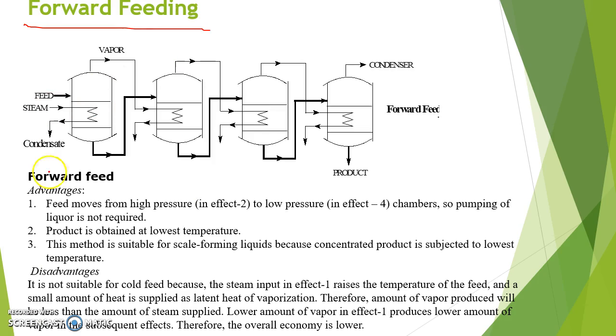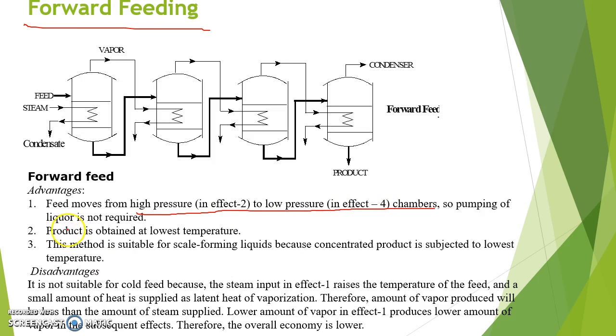In forward feeding, the feed enters the first effect evaporator and the product is collected from the last effect evaporator. The advantages of forward feeding are: feed moves from high pressure to low pressure chambers so pumping of liquor is not required, and the product is obtained at the lowest temperature. This method is suitable for scale-forming liquids because the concentrated product is subjected to the lowest temperature.